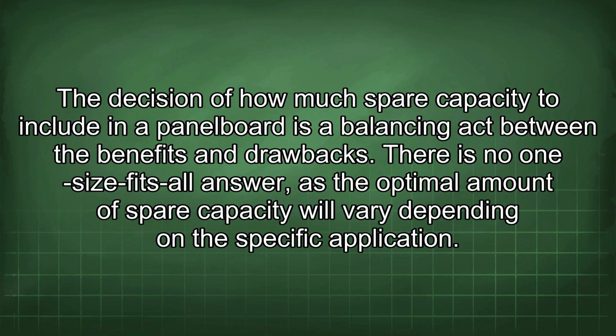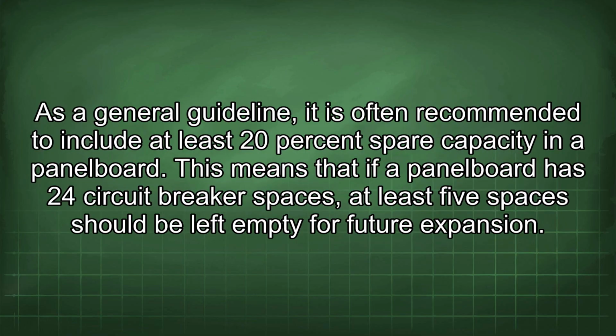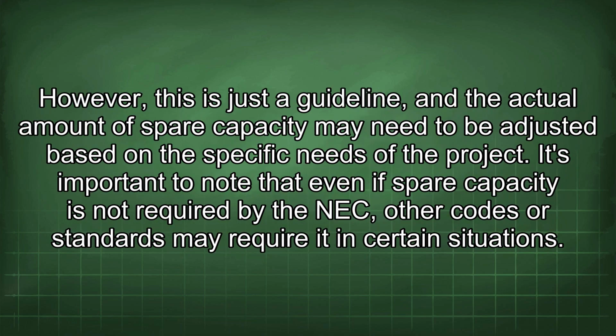The decision of how much spare capacity to include in a panel board is a balancing act between the benefits and drawbacks. There is no one-size-fits-all answer, as the optimal amount of spare capacity will vary depending on the specific application. As a general guideline, it is often recommended to include at least 20% spare capacity in a panel board. This means that if a panel board has 24 circuit breaker spaces, at least 5 spaces should be left empty for future expansion. However, this is just a guideline, and the actual amount of spare capacity may need to be adjusted based on the specific needs of the project.